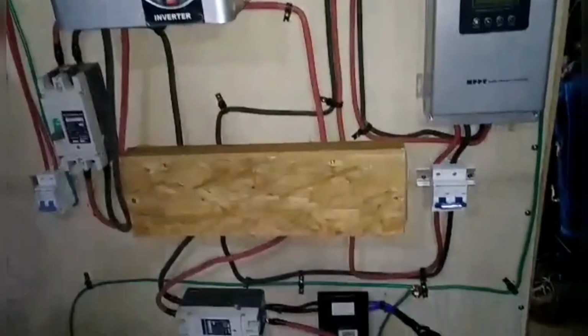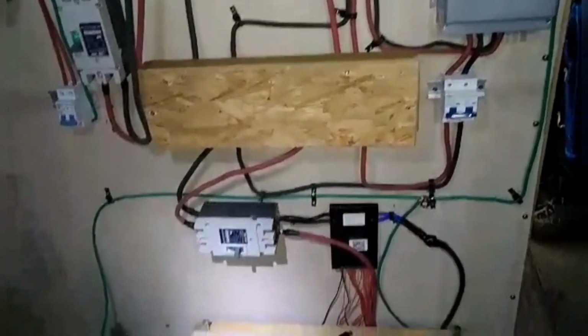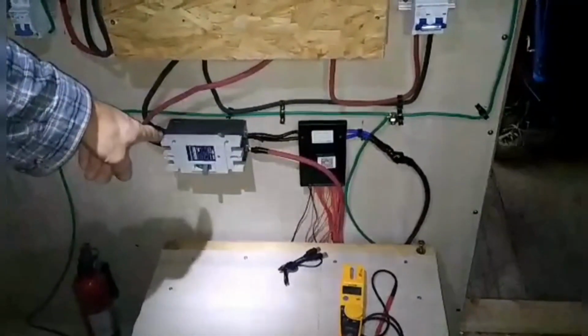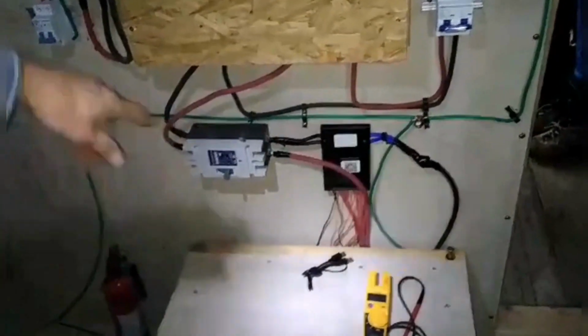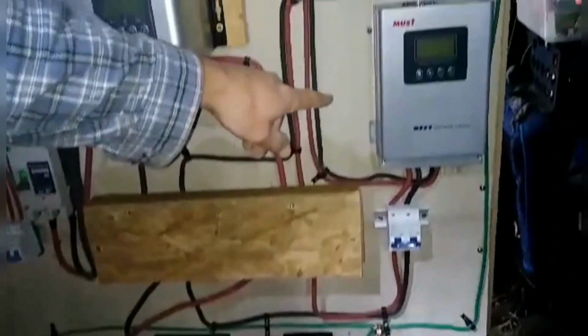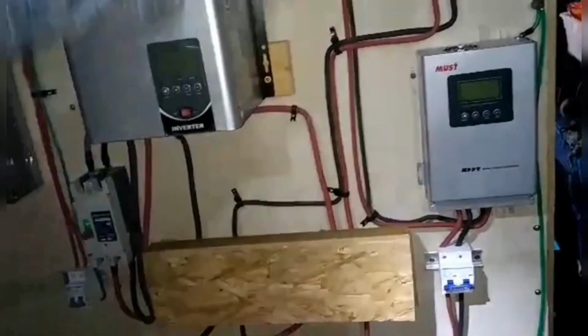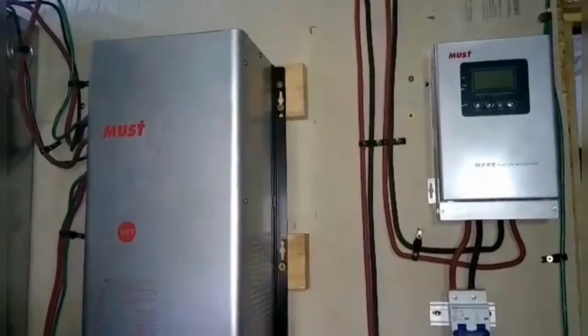So the very first thing I'm going to do, now that I've double checked all my connections and wiring, is to open up this breaker here, which will allow power from the battery to come up into the controllers. Then I'm going to power on the controllers and go through the menus on those and get those set up for the batteries that we have.